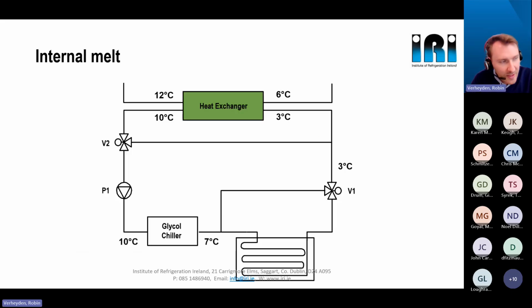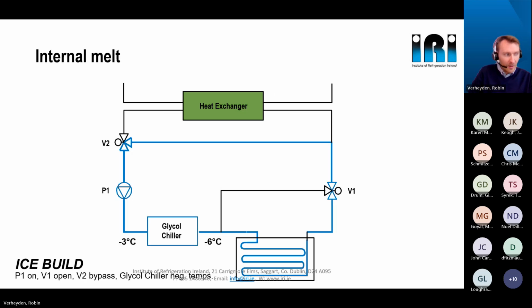Now, we will translate this into a typical internal melt schematic. As you can see over here, we will use a glycol chiller in series with an ice tank, in combination with some bypass lines, but we will talk about that more in the next slide. So this is typically how we will build the ice. We will modulate the V2 three-way valve to prevent the heat exchanger from freezing. Then we will activate the pump and the chiller to deliver negative temperatures, typically -6 degrees, to the ice tank to start building the ice.